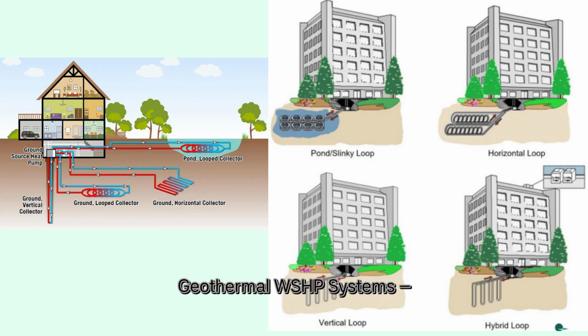Geothermal WSHP systems, the ultimate upgrade. When paired with geothermal loops, WSHP systems reach their highest efficiency. Here, the building's hydronic loop exchanges heat directly with the earth or nearby water bodies, like ponds. The earth remains at a stable 60 degrees Fahrenheit year-round, much easier for the heat pump to work with compared to outdoor air that can vary from 0 degrees F to 100 degrees F.